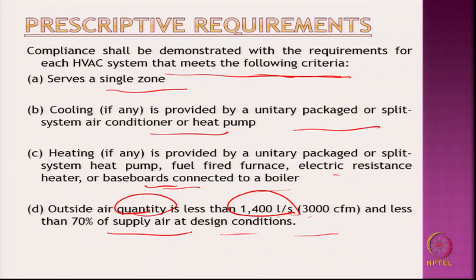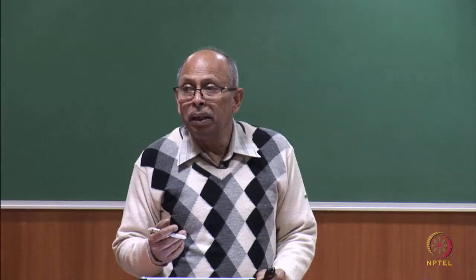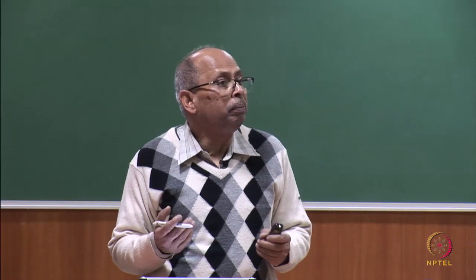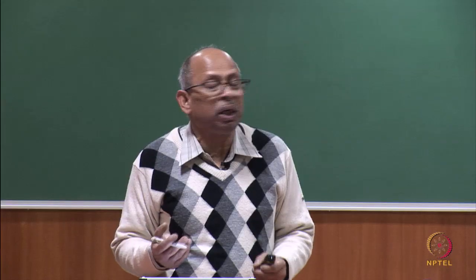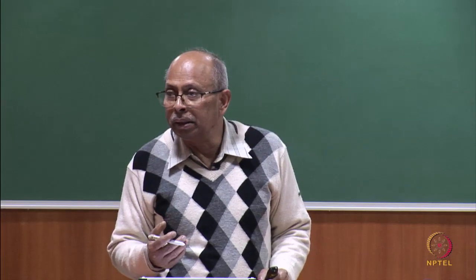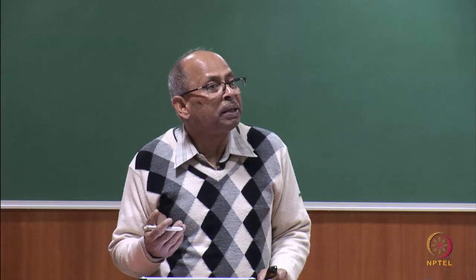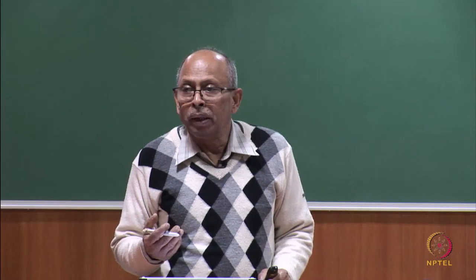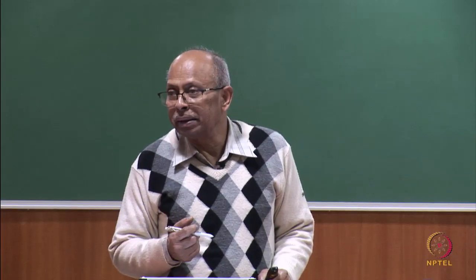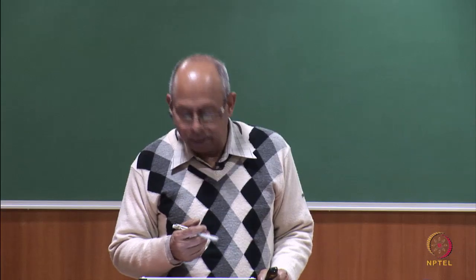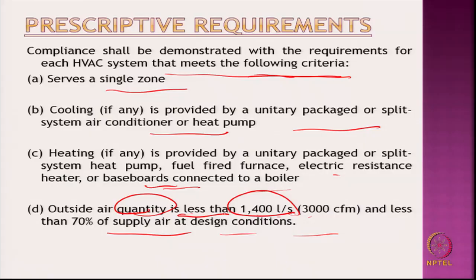Now, one thing you need basically is a minimum ventilation requirement, or fresh air requirement, for hygienic condition. But if you increase the fresh air requirement, the cost of cooling increases, and the energy requirement will increase. So, that is why the flow rate of less than 1400 liters per second is again controlled, right, and less than 70% of the supply air at design condition.